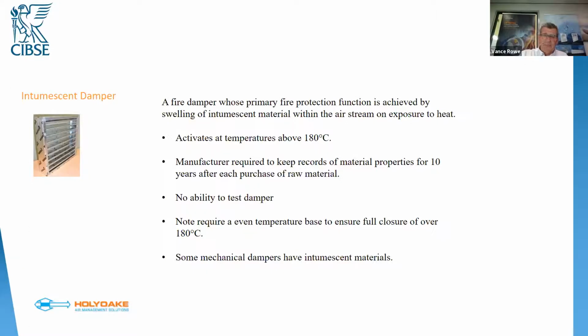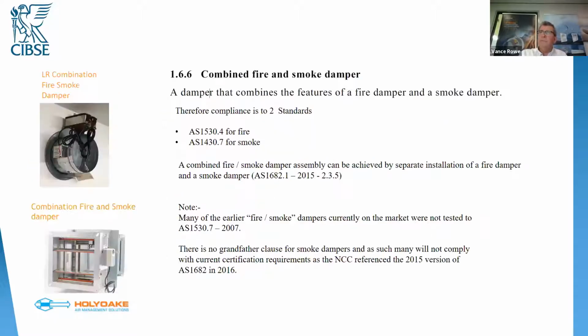All right. Some mechanical dampers now have intumescent materials. In fact, our range of fire dampers has an intumescent seal on the mounting angle. Combined fire and smoke dampers. Again, I really can't harp on this point enough, because I do see a lot of errors in this area of our industry. They need to be compliant to two standards. So that's AS 1530.4 for fire and AS 1530.7, 2007 for smoke.